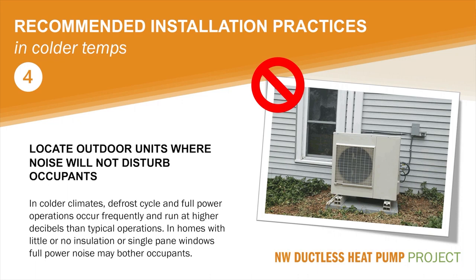If you find yourself in a situation where you have no alternative but to locate the outdoor unit near a bedroom, be sure to ask the homeowner if the person that sleeps in the room is prone to waking up from noises. If they are a so-called light sleeper, you may want to go back and look for an alternative installation location. Typically, a wall adjacent a closet or bathroom is nearby, and locating the outdoor unit adjacent one of these walls may remedy the problem.